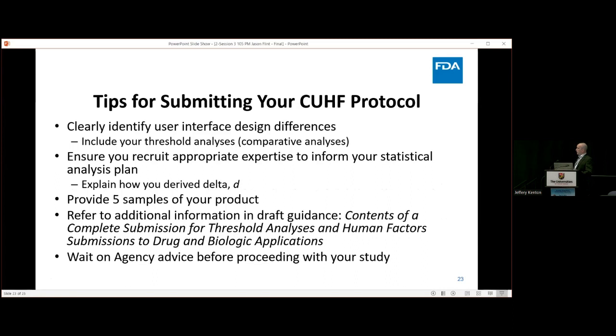So, tips for submitting your CUHF protocol include your threshold analysis. We need to clearly understand what the user interface design differences are so that we can then assess whether the study has been designed appropriately to address those. Make sure that you recruit appropriate expertise to inform your statistical analysis plan, and explain and justify how you derived delta and how you derived your sample size. Provide 5 samples of your product.